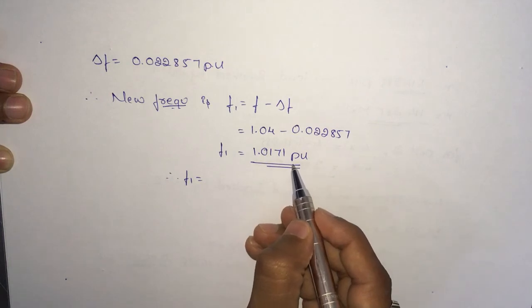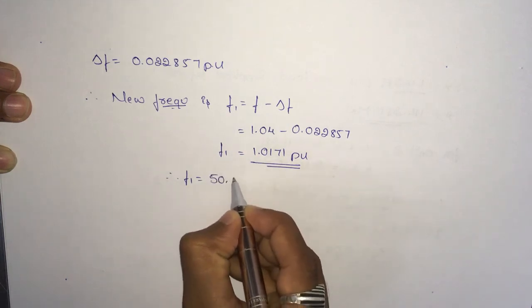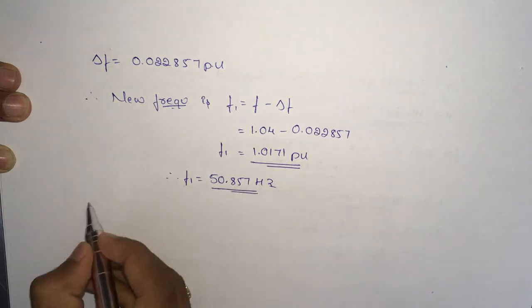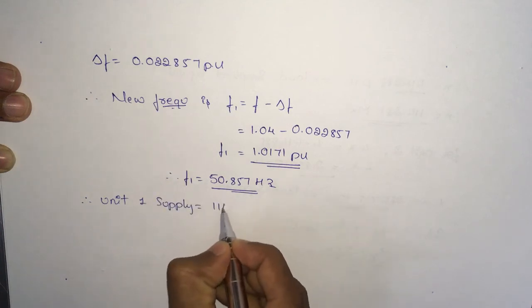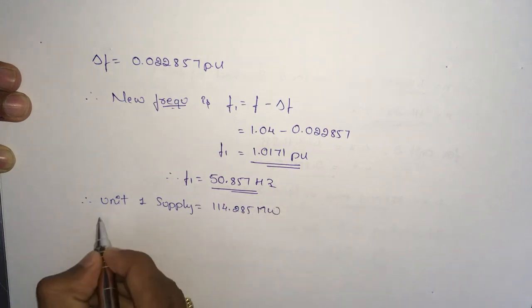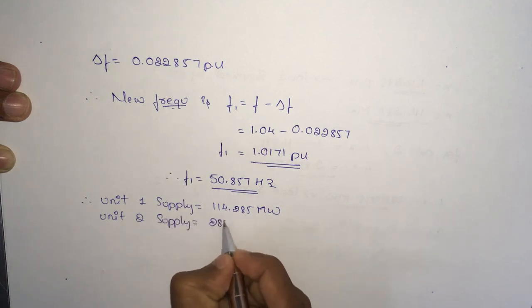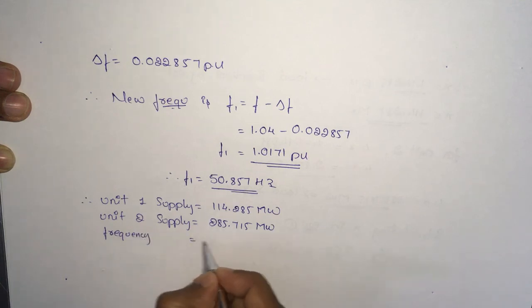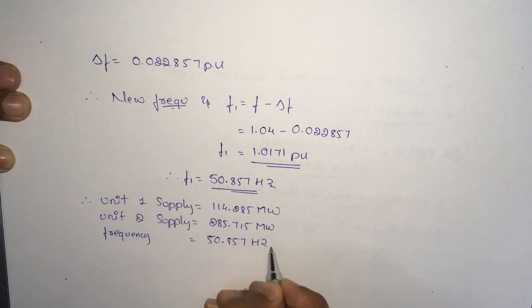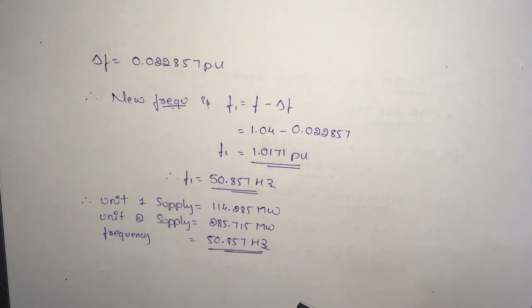Therefore, unit 1 supplies 114.285 megawatt, unit 2 supplies 285.715 megawatt, and the system frequency is 50.857 Hertz. Thank you for watching — if you have any doubts, please put a comment in the comment box and we'll discuss.